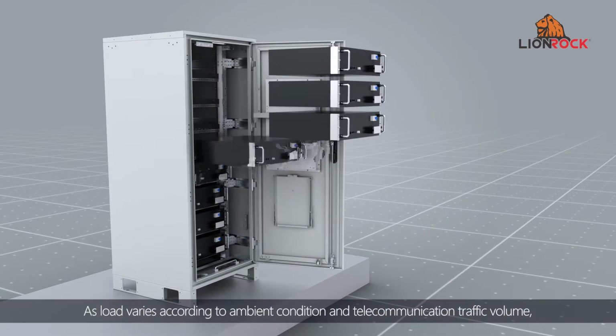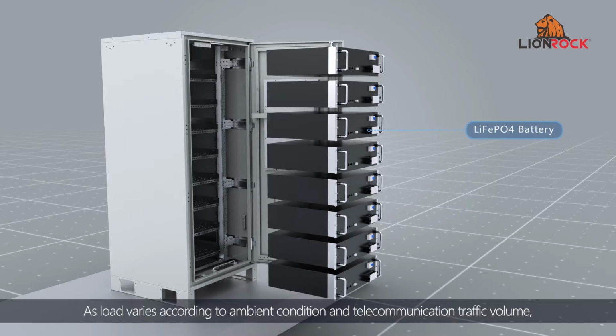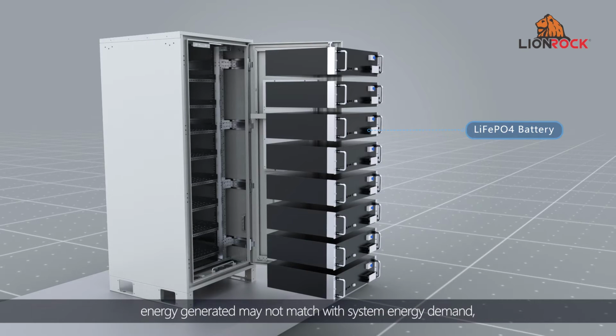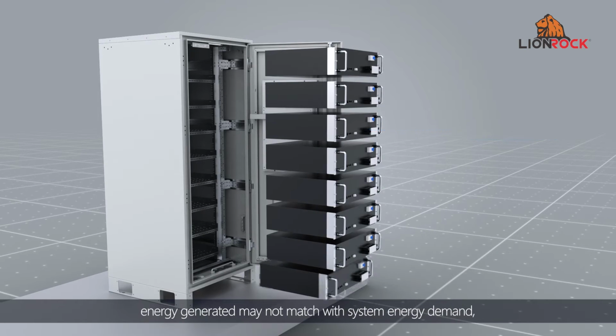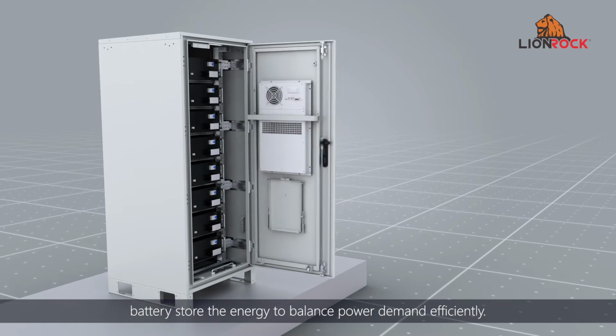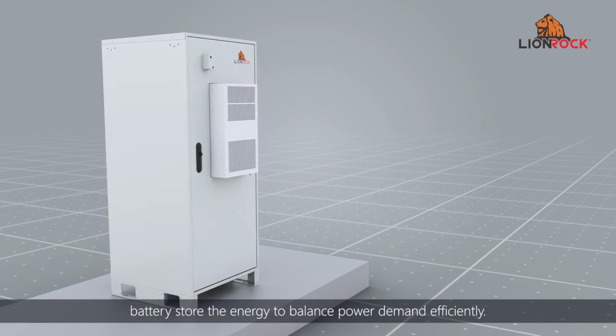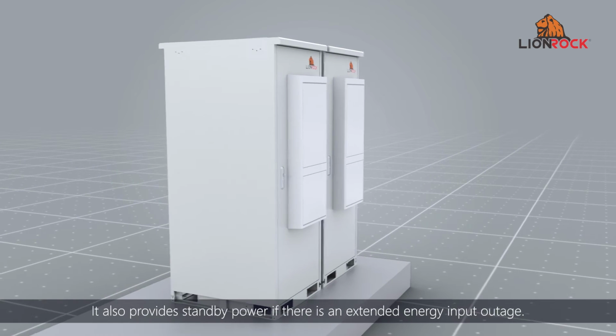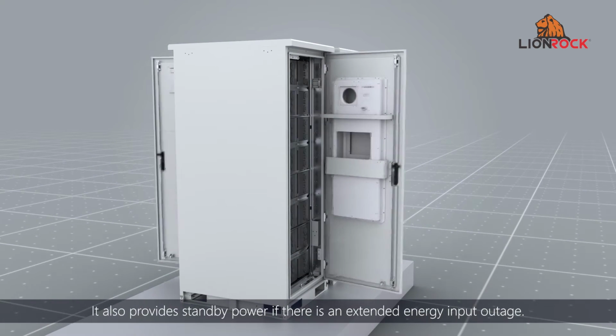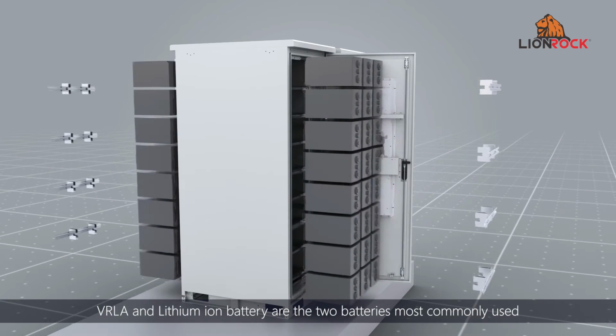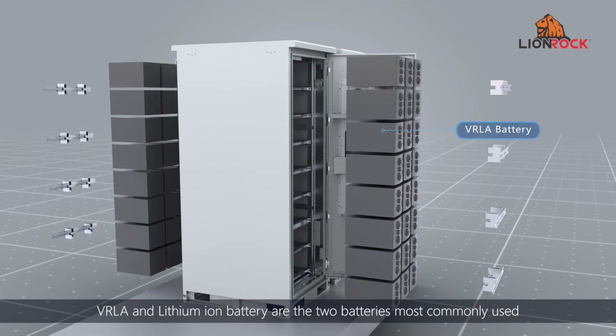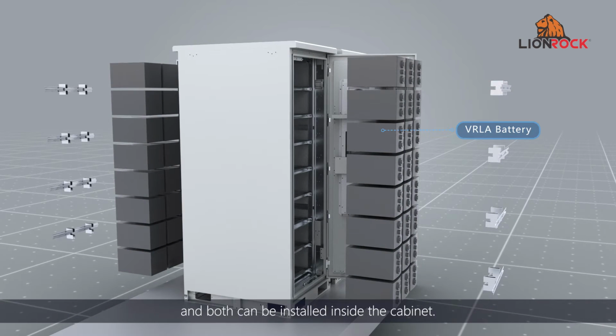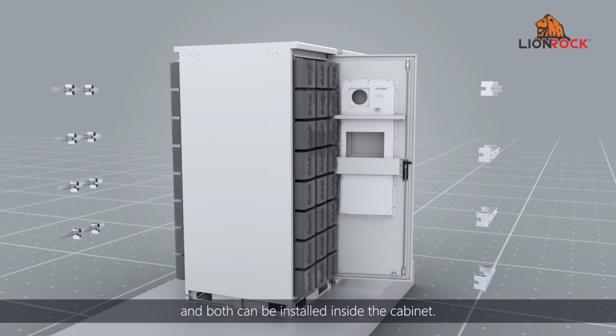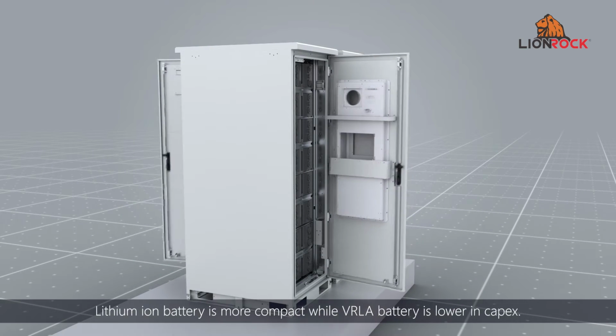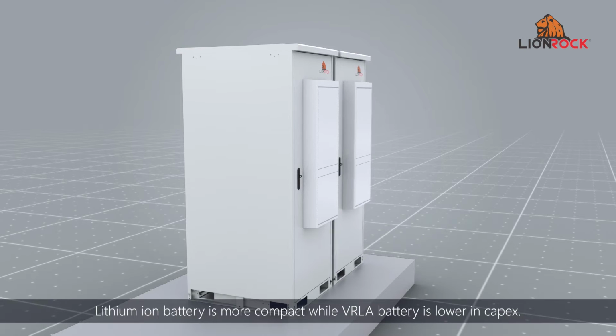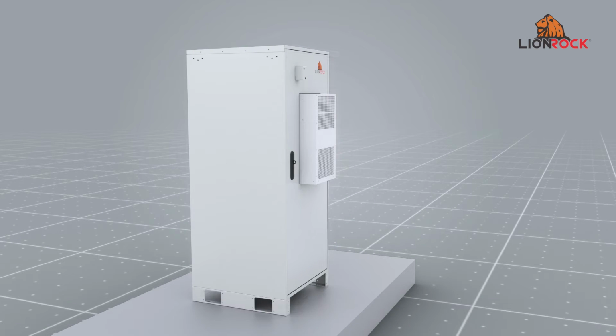As load varies according to ambient condition and telecommunication traffic volume, energy generated may not match system energy demand. Batteries store the energy to balance power demand efficiently. They also provide standby power if there is an extended energy input outage. VRLA and lithium-ion batteries are the two most commonly used, and both can be installed inside the cabinet. Lithium-ion battery is more compact, while VRLA battery is lower in capex.